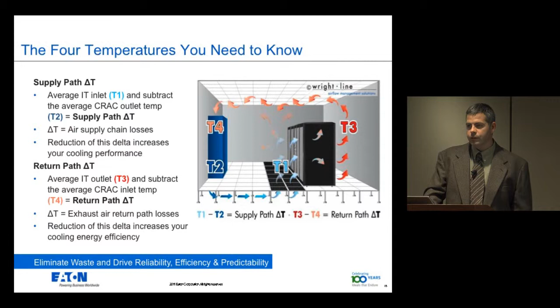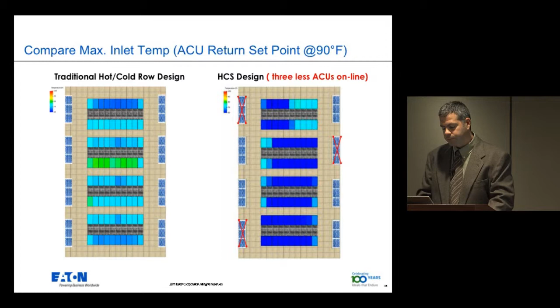So here's one example of a real data center that some folks at Wright Line worked on. What we see, the light green racks are racks that are operating, and I think the temperature was taken at mid-level, outside of ASHRAE's recommended range. There are different ranges that you have now, but the green racks are outside the recommended range. So what this customer did was use hot aisle containment in this case. Through hot aisle containment, they were able to get better, more uniform performance, and still shut off 3 air handlers that were on the floor completely. And that's the magic of heat containment.